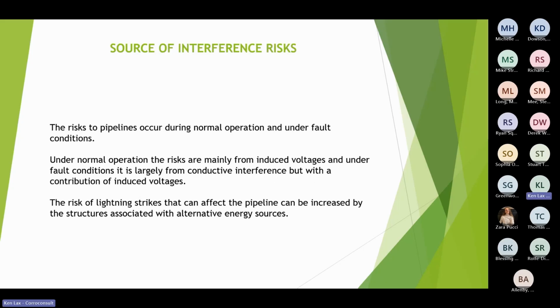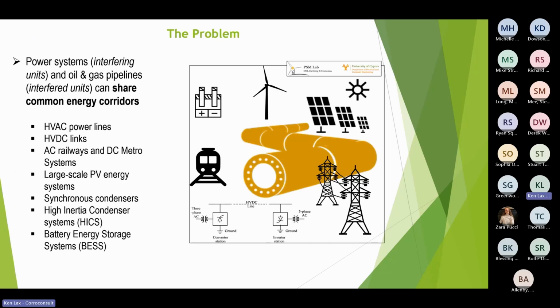Right, the risks to the pipelines under normal operation and fault conditions are essentially separated into inductive under normal operation, and under fault conditions there would be conductive. And as I mentioned, the DC is there all the time. And I've mentioned earlier that lightning strikes can affect the pipeline because the risk is increased by neighboring structures. You can see here a little image illustrating all of these things. We've included railways as well because they can be a source of interference, but we're mainly talking about solar farms and things like that.